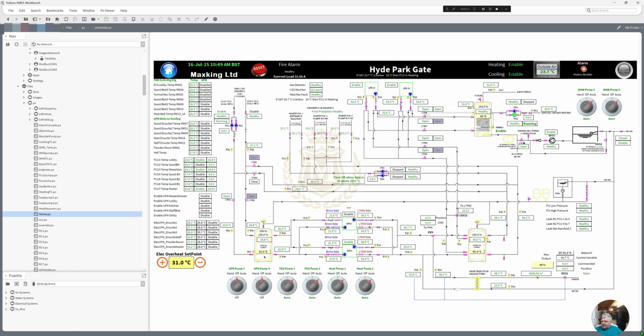So chilled water, our set point is at 16 degrees. So our PI loop is at 100% because we want 16-degree water or below before this PI loop decides to start falling and switching off the heat pump. The heat pump, like I said, is currently delivering 17 degrees. This is mixing in the tank, the returns mixing in the tank to give us our 19 degrees temperature there.